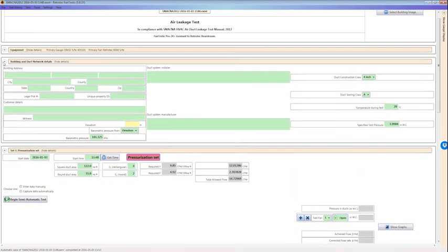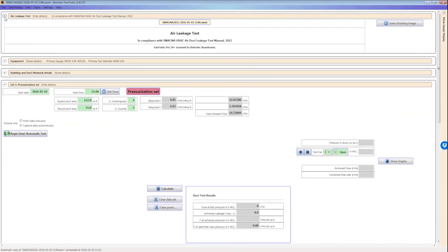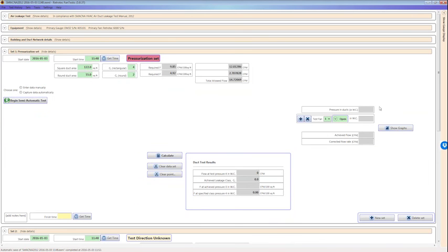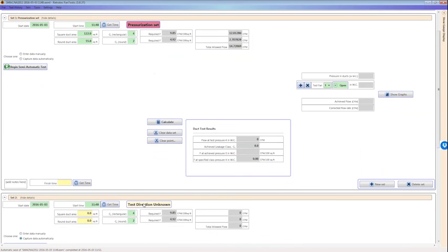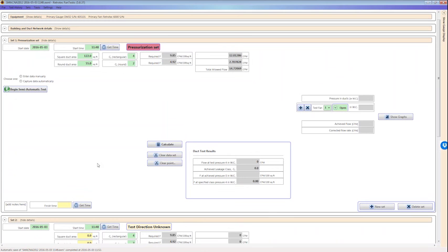So this may come from your gauge, and now you can enter like say 15. Or we make it 13. Make it 13. 13 CFM? Yeah. And now hit calculate. So what you're doing is you can either enter the pressure you had on the gauge based on that range, or I can get the CFM from my gauge. And you've noticed now we actually passed, getting information directly from the gauge.